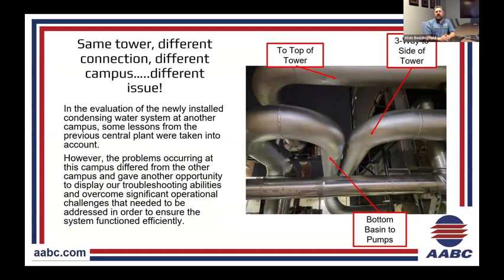Obviously, we're having flow issues at a tower. It's a different type of issue, but we're having similar issues. So we already know, okay, well, let's go through the engineering submittal data for the tower again, because obviously that was something we utilized. That's something that sometimes isn't included when they just pull out the submittal. They just give you the performance. That engineering data sometimes has to be dug through to pull the data to actually get the actual capabilities of the tower. We all understand the performance works, but what can the tower do?